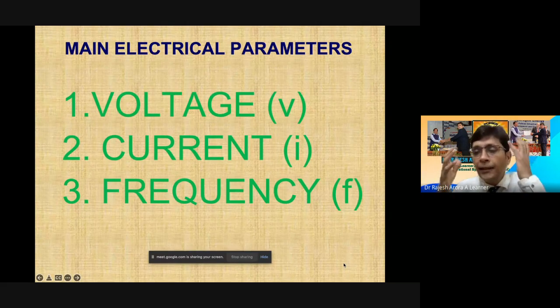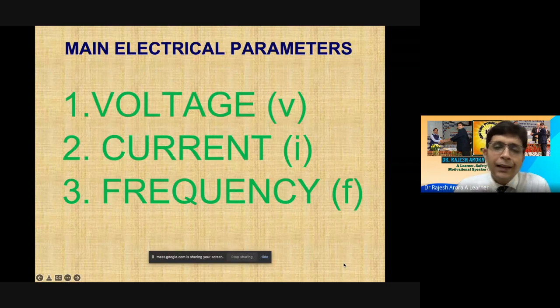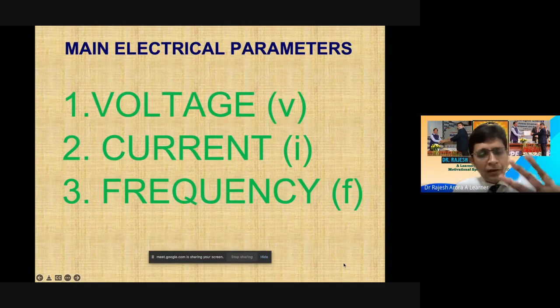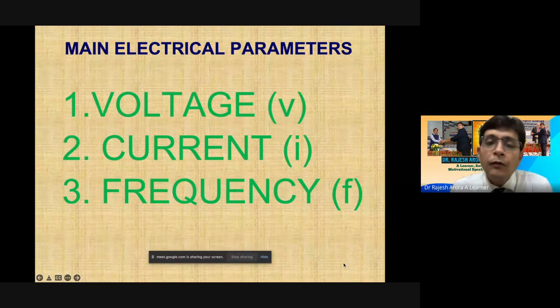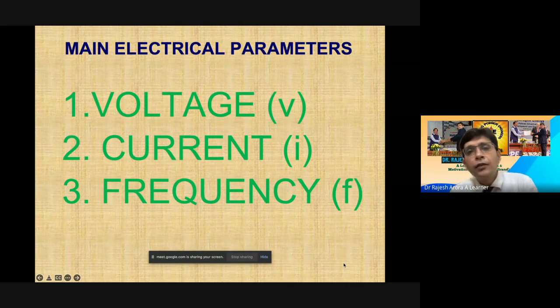When we talk about electrical accidents, fire, loss of equipment, the story revolves around these three factors, apart from negligence and human errors. I am now talking about technical things first. When you talk about voltage, you have to provide good insulation. When we talk about current, you have to provide sufficient cross-sectional area that has the capability to withstand the short circuit current that may happen in your system.